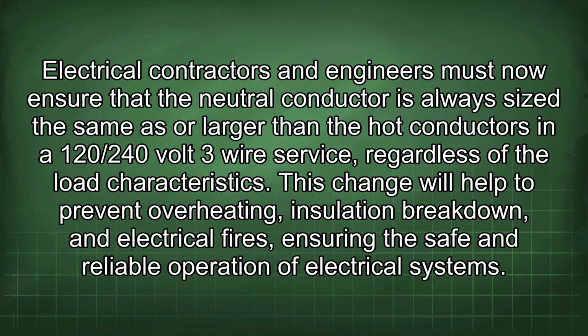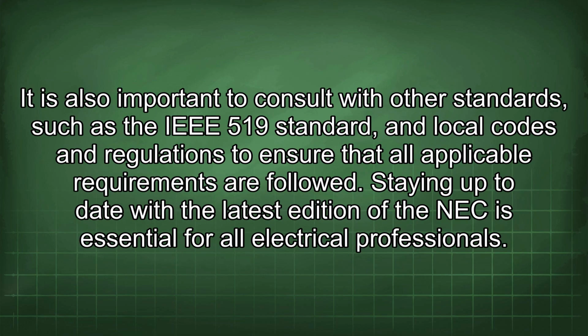Electrical contractors and engineers must now ensure that the neutral conductor is always sized the same as or larger than the hot conductors in a 120/240 volt 3-wire service, regardless of the load characteristics. This change will help to prevent overheating, insulation breakdown, and electrical fires, ensuring the safe and reliable operation of electrical systems. It is also important to consult with other standards, such as the IEEE 519 standard and local codes and regulations, to ensure that all applicable requirements are followed.